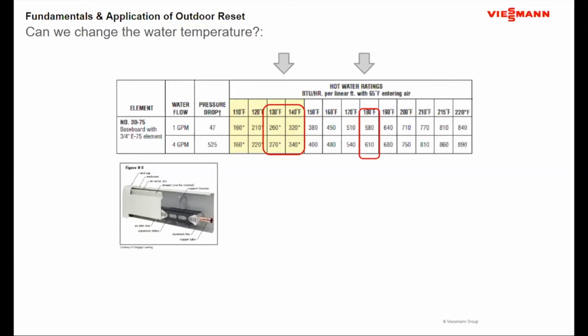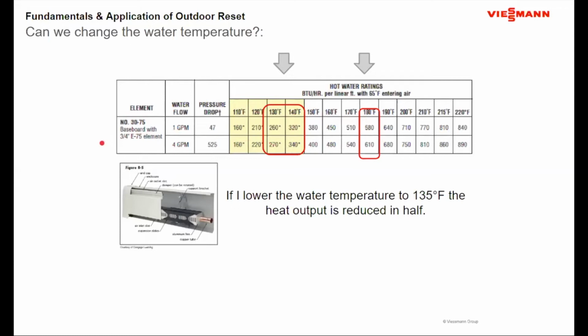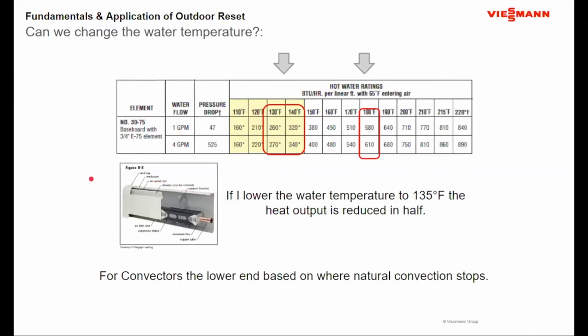So if I drop the water temperature by a given amount, I get a fairly consistent response where the heat emitter drops about the same ratio as well. So we start to look at changing the water temperature as a methodology of resetting the heat emitter's output. By dropping the water temperature, I get a fairly consistent response out of the heat emitter, reducing the amount of energy.